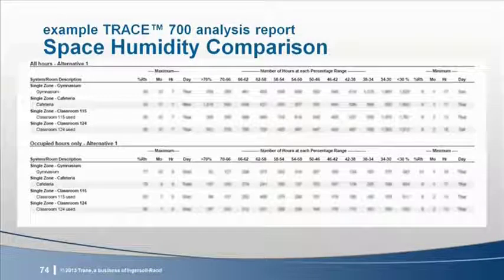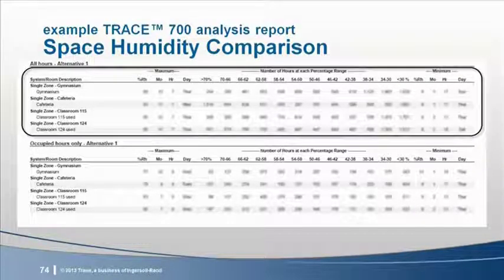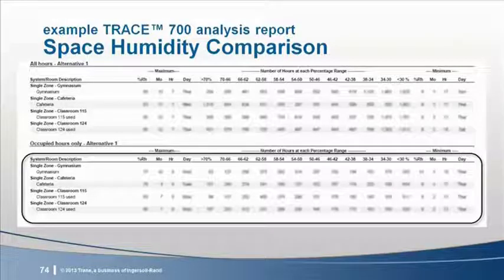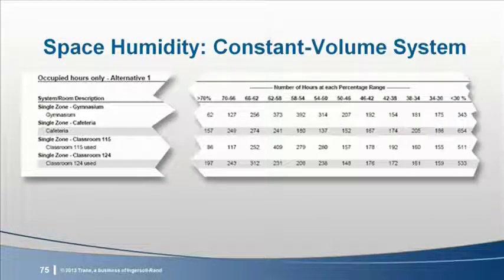This report allows us to review the space humidity values throughout the simulation. Relative humidity for each space is reported for all hours of the simulation and all occupied hours. Let's take a closer look at the occupied hours for a constant volume system versus a SingleZone VAV system. Here are the results. The report provides the maximum and minimum relative humidity values for each space at the time of occurrence. The center section shows us the number of hours within each 4% bin.